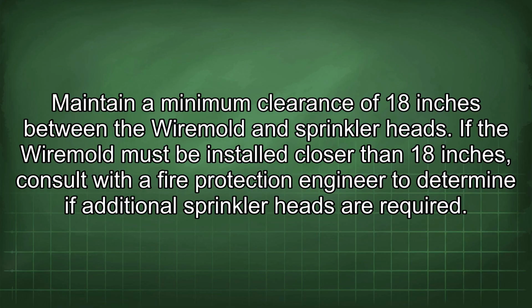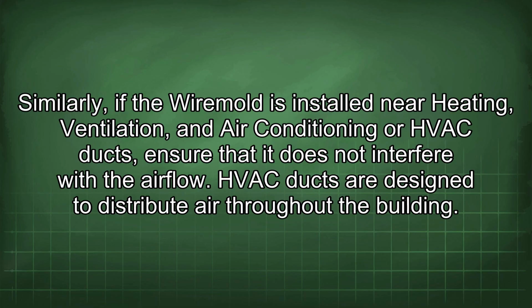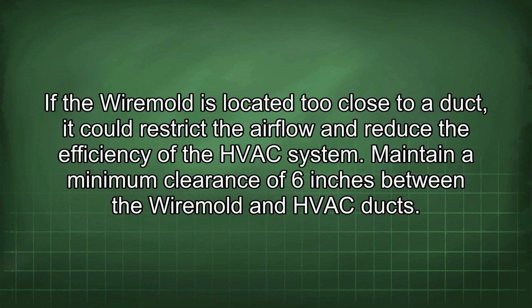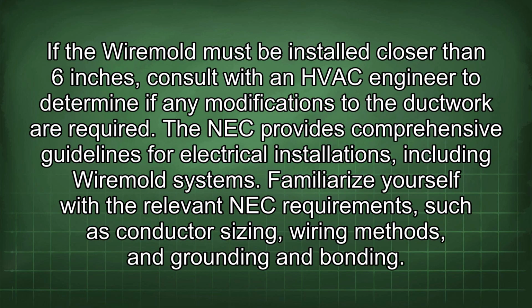Similarly, if the Wiremold is installed near heating, ventilation, and air conditioning or HVAC ducts, ensure that it does not interfere with the airflow. HVAC ducts are designed to distribute air throughout the building. If the Wiremold is located too close to a duct, it could restrict the airflow and reduce the efficiency of the HVAC system. Maintain a minimum clearance of 6 inches between the Wiremold and HVAC ducts. If the Wiremold must be installed closer than 6 inches, consult with an HVAC engineer to determine if any modifications to the ductwork are required.